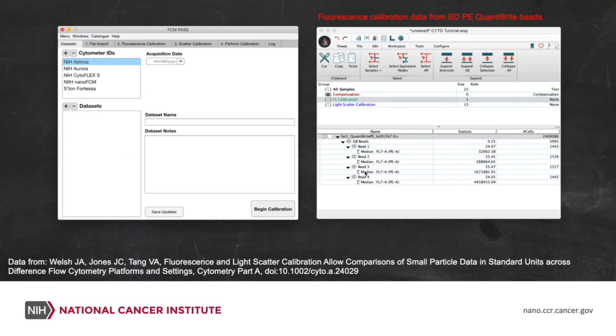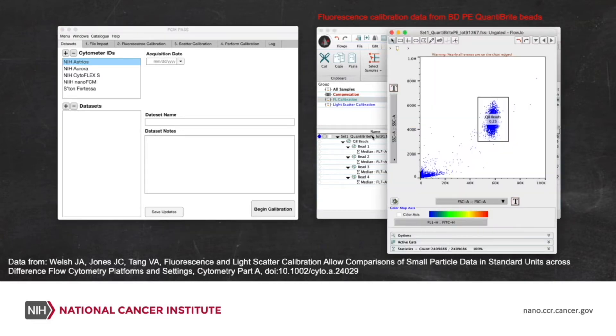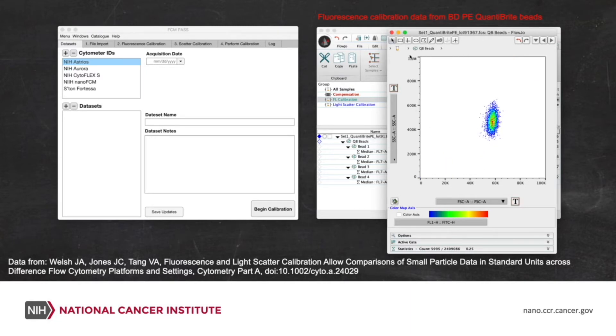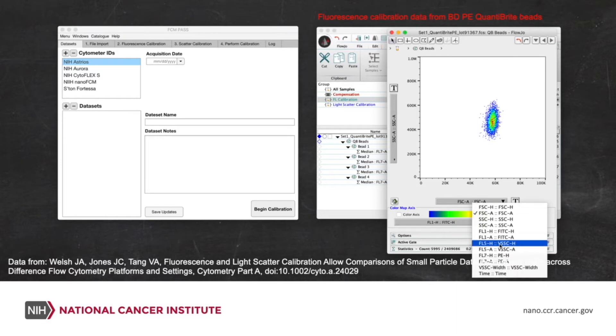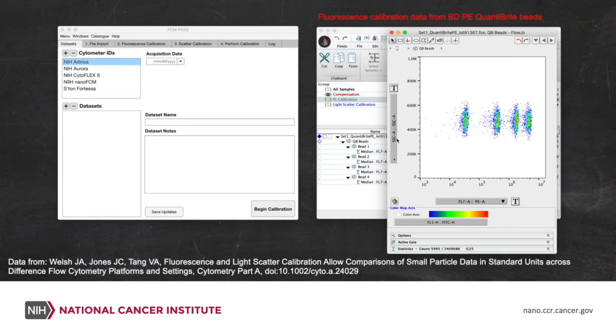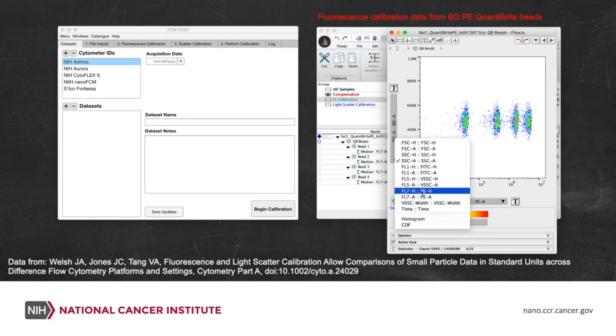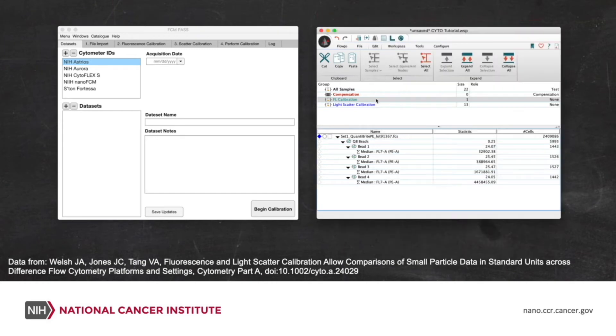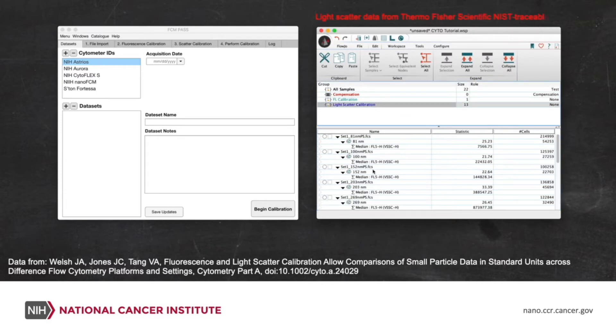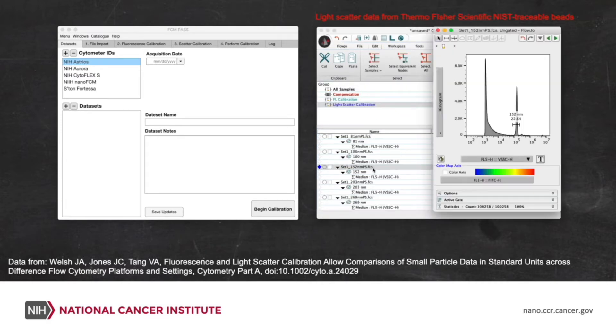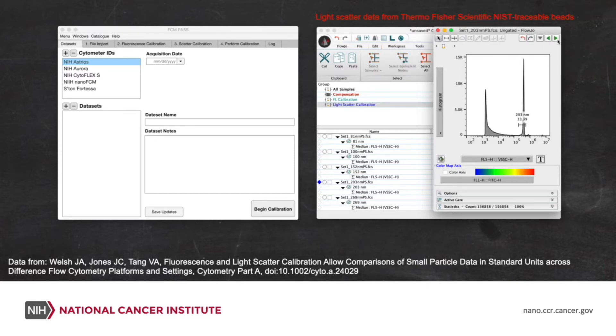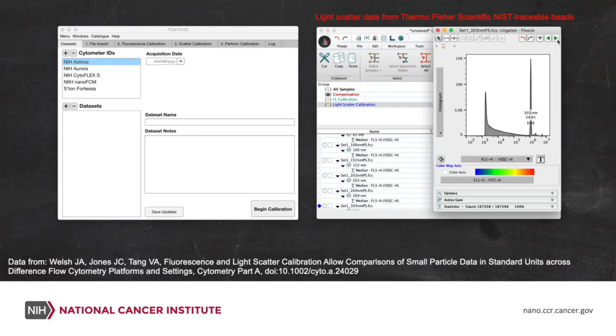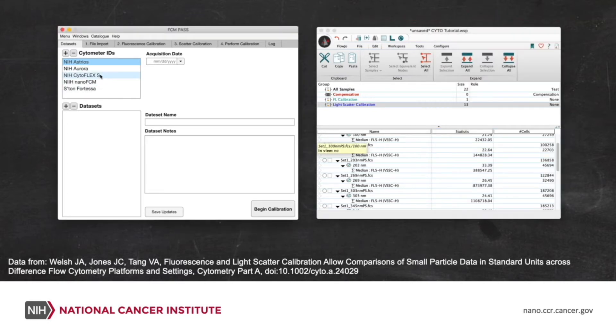These are some BD QuantiBrite MESF beads and I'm just going to show you how they were gated. So we're gated on forward scatter and side scatter here. We'll just look at the PE channel and turn this into a histogram, and you can see each of the gates for the beads. And just to do the same with the NIST traceable beads, this is the violet side scatter height. We've used the height here because we're defining the trigger, whereas the fluorescence channel we are using the area statistic. And for all of these populations we're using the median.